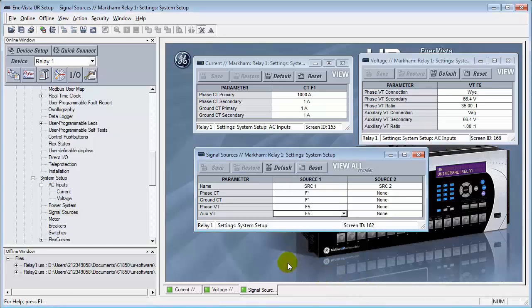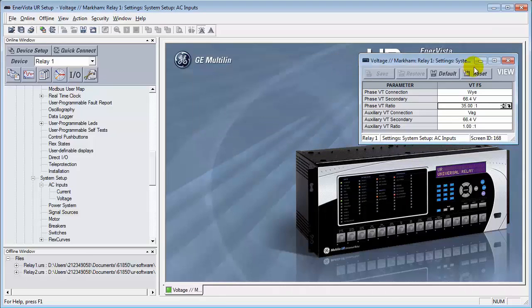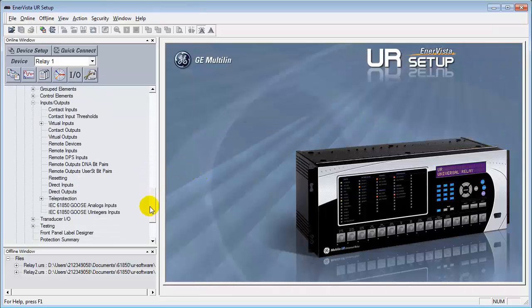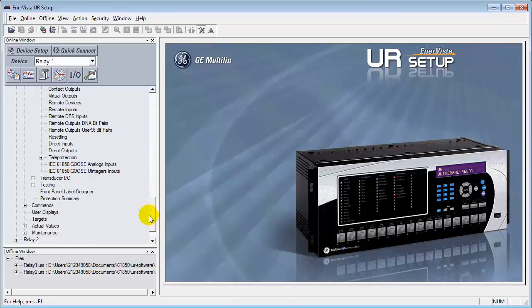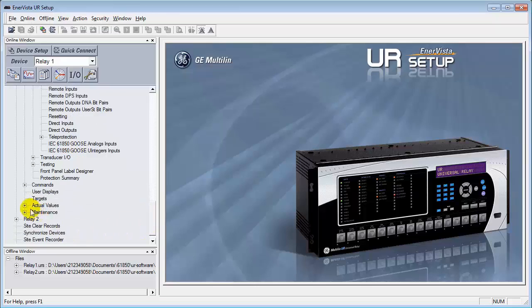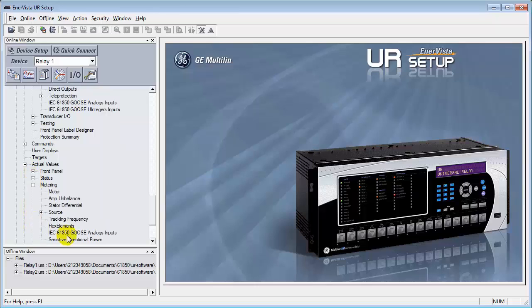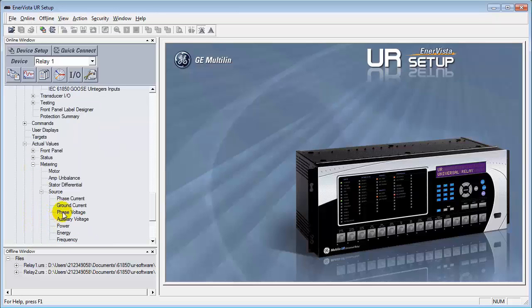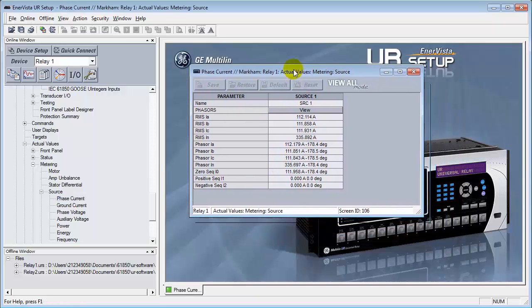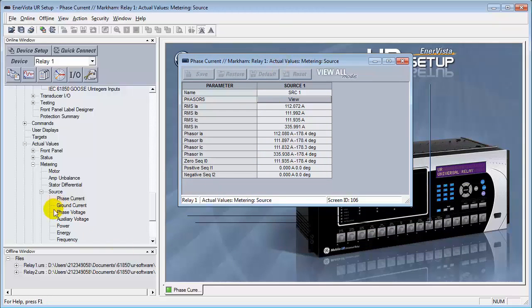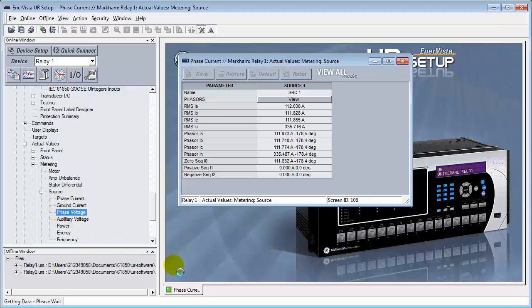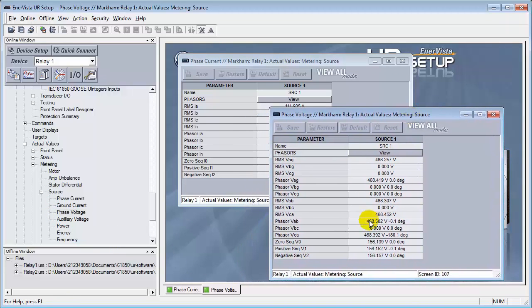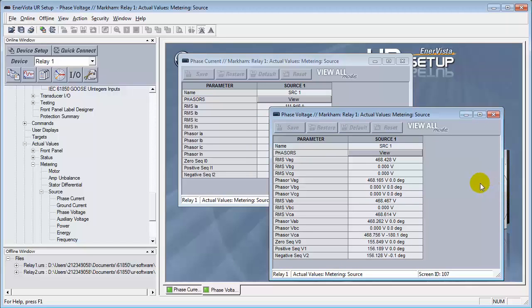Now, let's verify that everything that we've programmed so far is actually working. Let's close these windows. First things first. Let's come down to the actual values section. Make sure we're actually creating these values. Coming down to the metering portion. Come down to the source. Good. We're getting some readings. Excellent. There's the currents. And let's confirm the voltage as well. And we're getting voltage readings as well. Perfect.